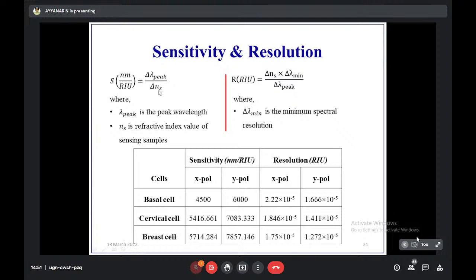NS is nothing but the particular refractive index value of the sample, like 1.38 to 1.39. The very first part displayed some values, the values calculated from the refractometer. That value is nothing but NS. Okay, this is the sensitivity formula.